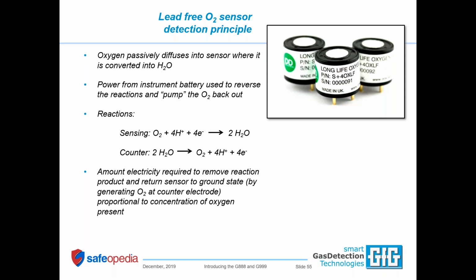When it comes to the oxygen sensor, I am so happy to be able to offer a standard 5-year warranty on the oxygen sensors that we use in the 888, the 999, and also in the G460. These are long life lead-free sensors manufactured by DDS. It's a great company. We're very, very happy with the performance and quality of DDS sensors. The whole idea behind the long life sensor is that you do not have a sensor with a lead anode, which is slowly consumed over the life of the sensor. And when the lead is gone, the sensor needs to be replaced. That is not the case with the lead-free sensor.